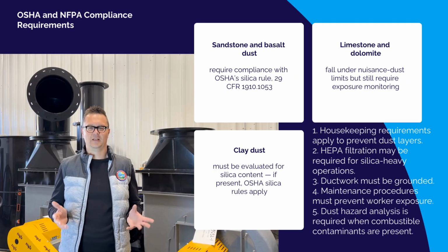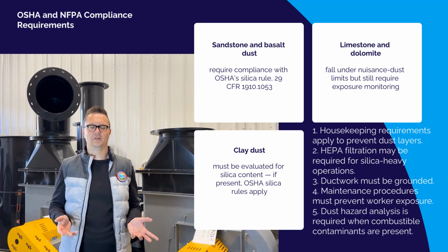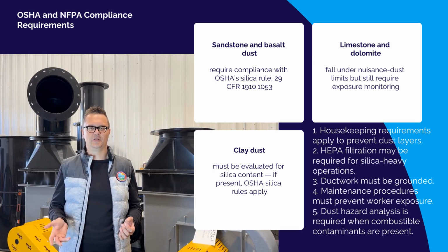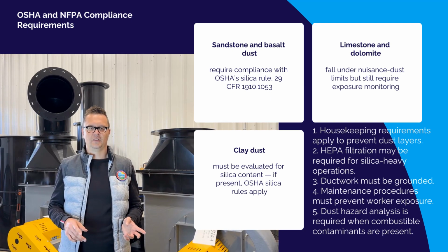OSHA and NFPA compliance requirements. Sandstone and basalt dust require compliance with OSHA's Silica Rule 29 CFR 1910.1053. Limestone and dolomite fall under nuisance dust limits but still require exposure monitoring. Clay dust must be evaluated for silica content. If present, OSHA silica rules apply across all 5 materials.